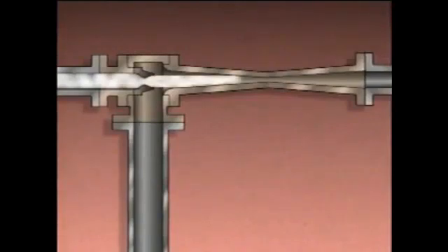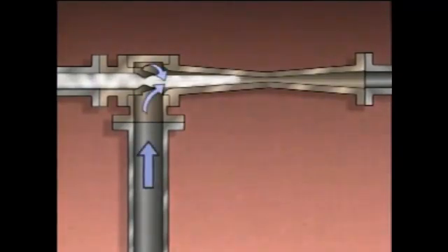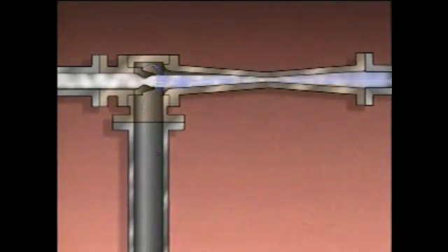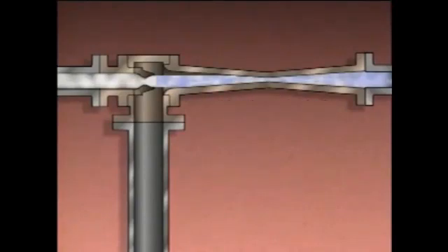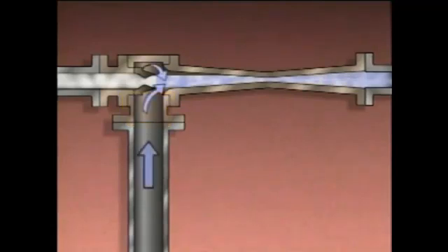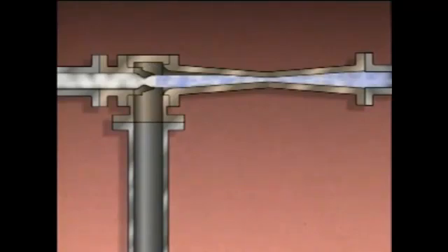As the steam passes through the nozzle, it is accelerated. As the fast-moving steam leaves the nozzle, it draws air in from the main condenser. As the steam and air mixture flows out of the air ejector, an area of low pressure forms in the air ejector suction port. This low pressure draws additional air in from the main condenser. This air also becomes entrained in the steam, and the process continues. The final result is that the pressure in the main condenser decreases.